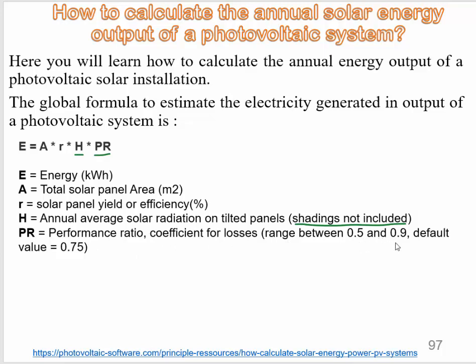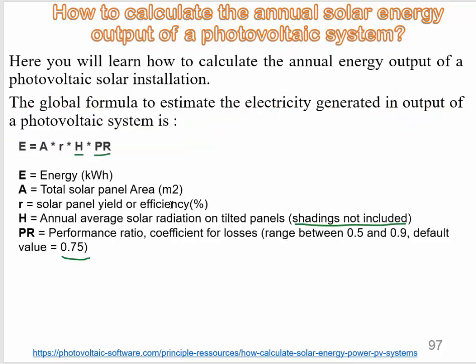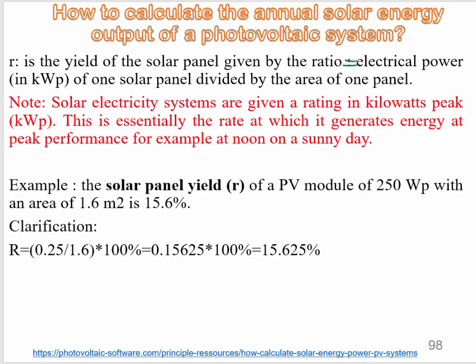The range of the PR factor is between 0.5 and 0.9, and the default value is 0.75. Now, how to calculate R: R is the efficiency or solar panel yield. To calculate R, R equals the electrical power in kilowatt peak (kWp) of one solar panel divided by the area of one panel.